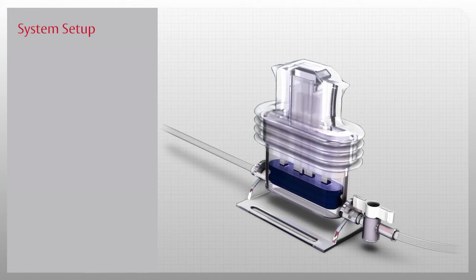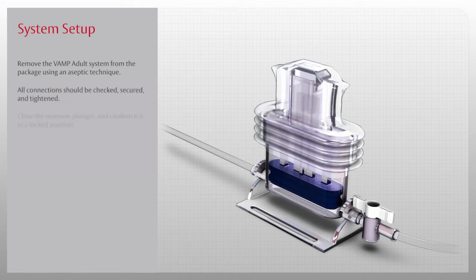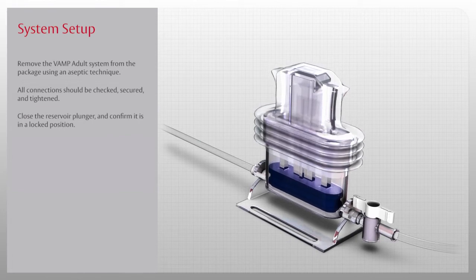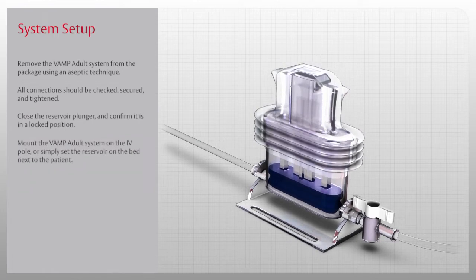Now that you've been introduced to the VAMP Adult System, let's start our in-service by setting it up. To begin, remove the VAMP Adult System from the package using an aseptic technique. All connections should be checked, secured, and tightened. Close the reservoir plunger and confirm it is in a locked position. Mount the VAMP Adult System on the IV pole or simply set the reservoir on the bed next to the patient.